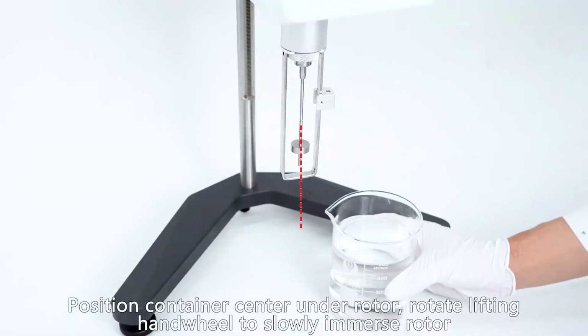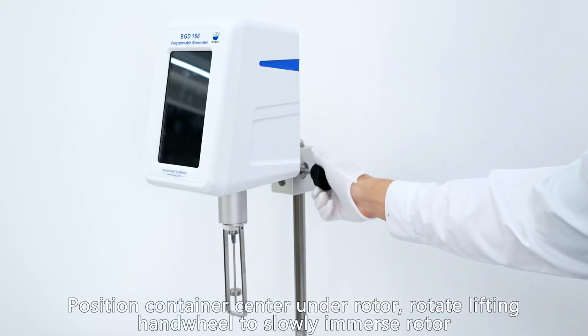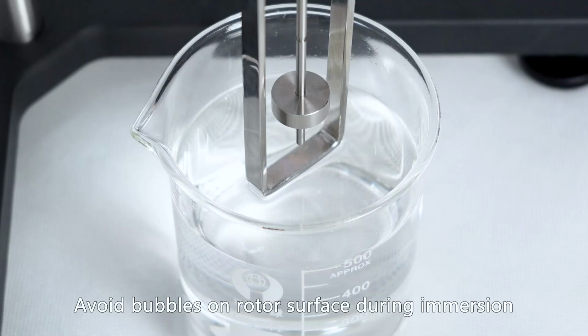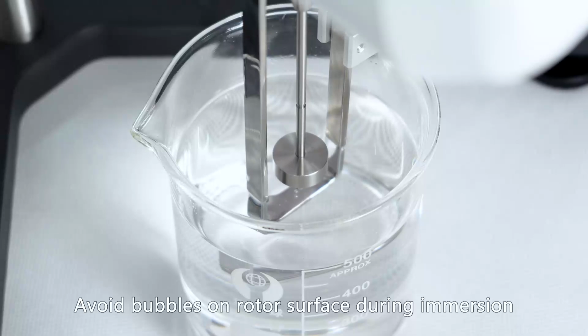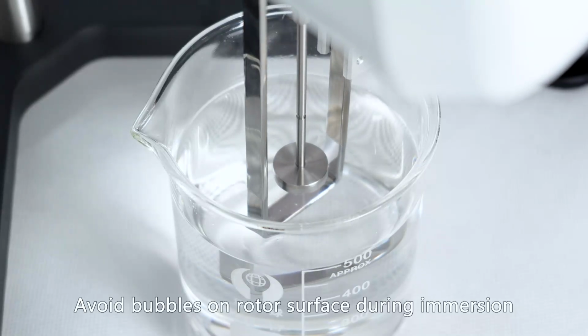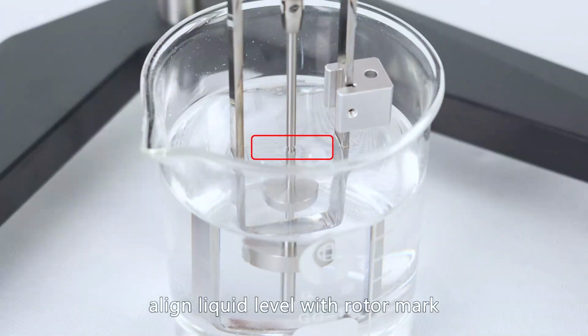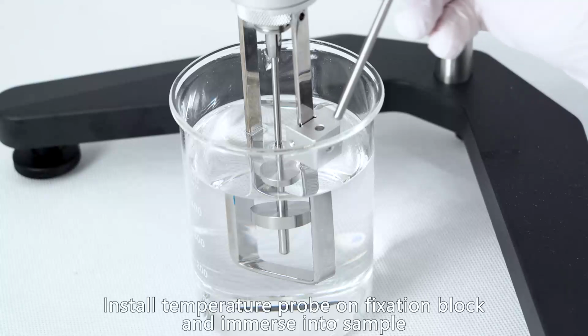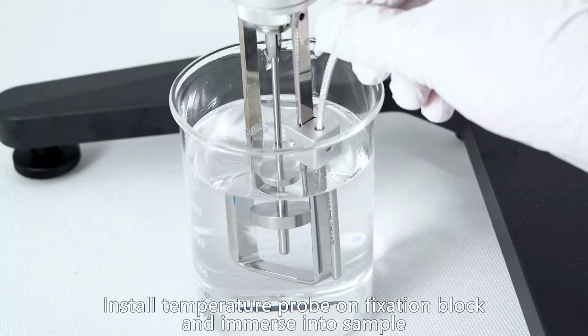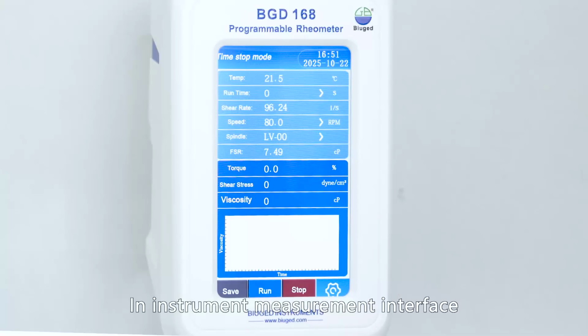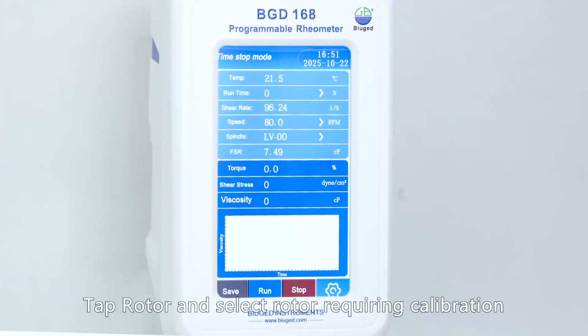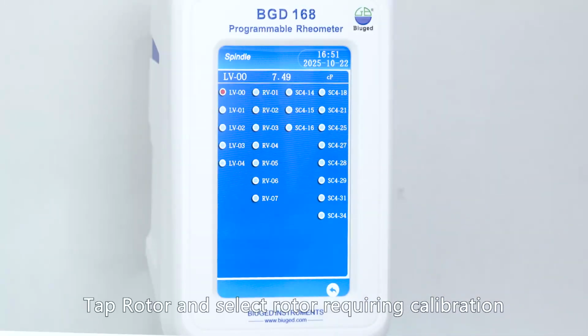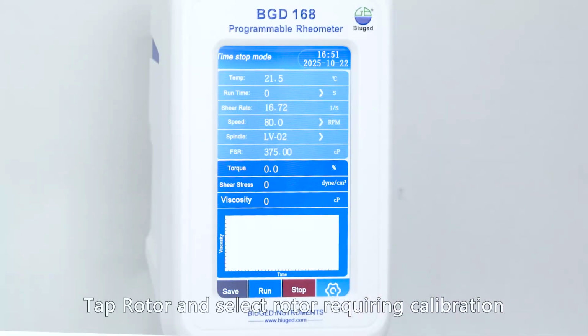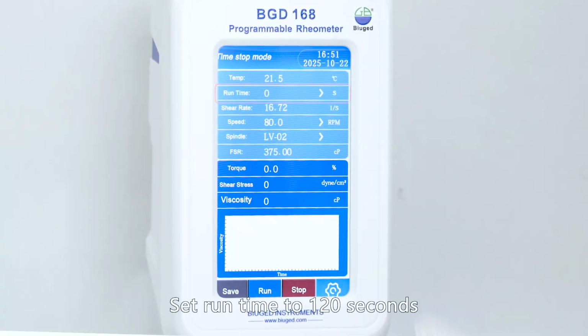Position container center under rotor. Rotate lifting handwheel to slowly immerse rotor. Avoid bubbles on rotor surface during immersion. Align liquid level with rotor mark. Install temperature probe on fixation block and immerse into sample. In instrument measurement interface, tap rotor and select rotor requiring calibration. Set run time to 120 seconds.